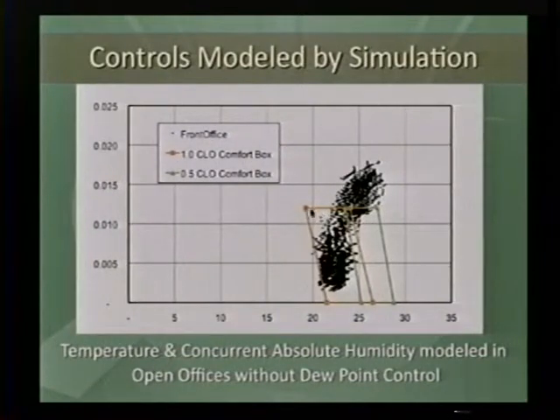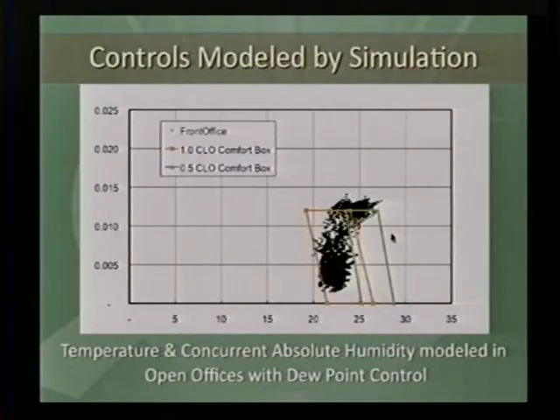And so the orange here is the ASHRAE Standard 55 winter comfort box for one clo, and the greenish here is the summer comfort box for 0.5 clo, and you can see there's quite a bit up here that is outside of what you want in that range. And we moved to a dew point control, both for better control of the interior in the office space and also for better warnings in natural ventilation if we were going to run into problems of condensation on a chilled slab. And this was sort of the first round with the dew point controller, and we could just throttle the temperature we wanted for the dew point down and bring all of that within that range.